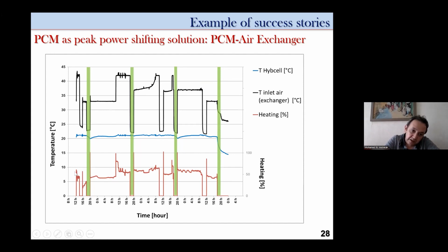So we are heating outside of the critical zone, and between 6 and 8 p.m. you can see that we have no heating, but the temperature is not dropping, because we are retrieving the energy stored, and we can see it here also and here. And in order to compare with and without the heat exchanger, you can see that when we don't have the heat exchanger and we are stopping heating, the temperature is dropping very, very fast. So we cannot only use ventilation without the heat exchanger. So we proved that during critical periods we can stop heating and use only ventilation, retrieving the energy stored.